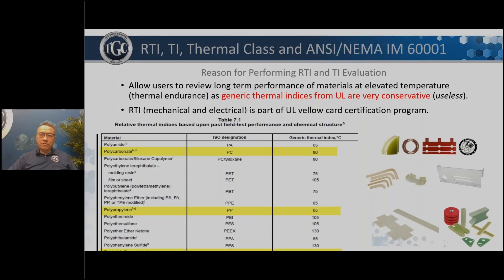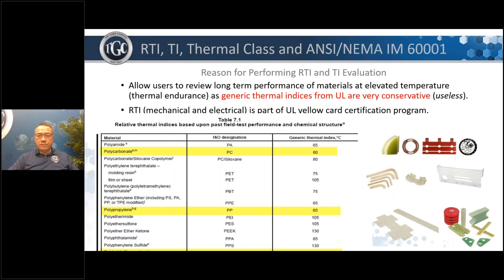For those of us who work with UL, who have a yellow card and who have to review the yellow card for our material or product application, we understand that on the yellow card in the right-hand column it says RTI. What does that mean? RTI is a reflection of the long-term thermal endurance of the material.